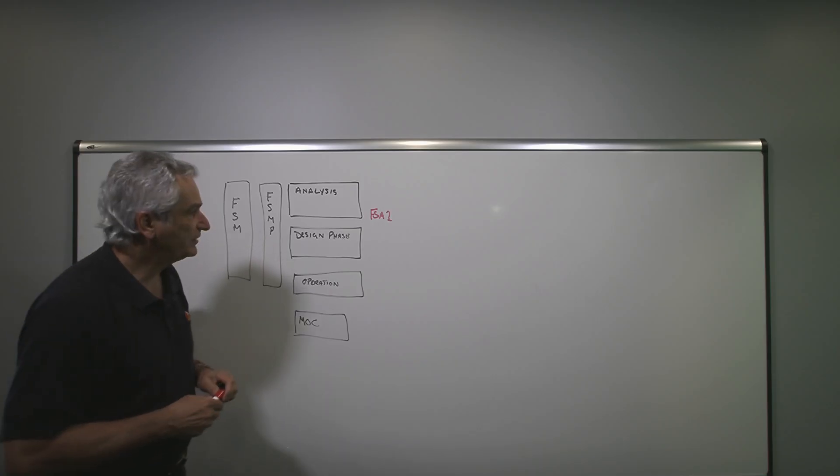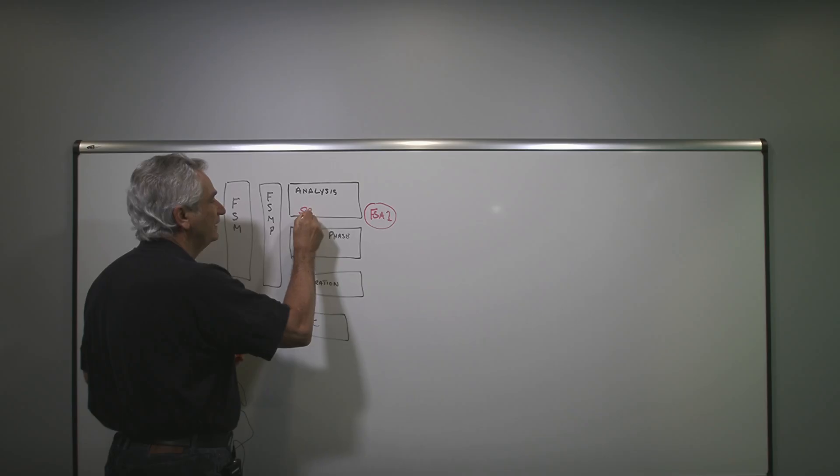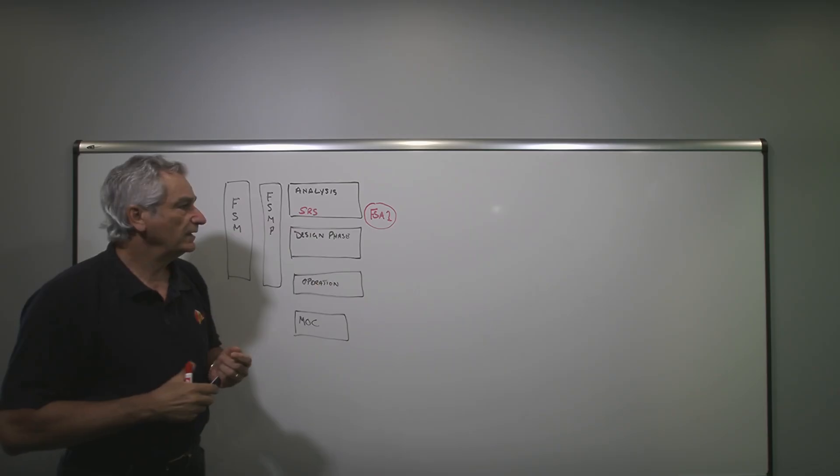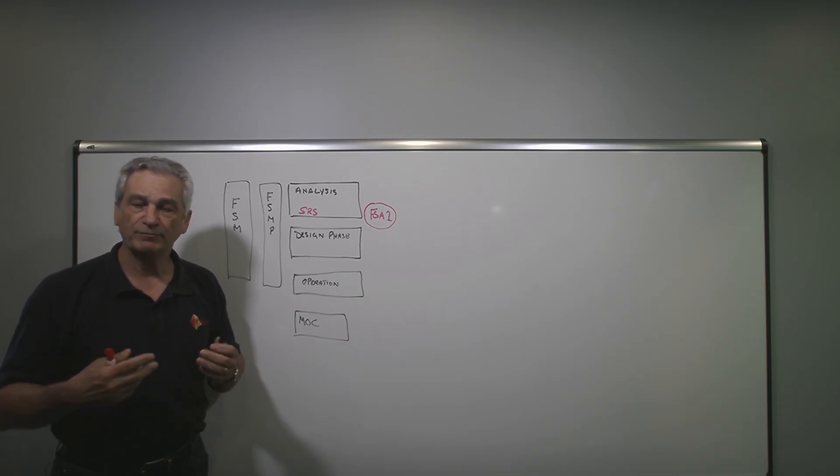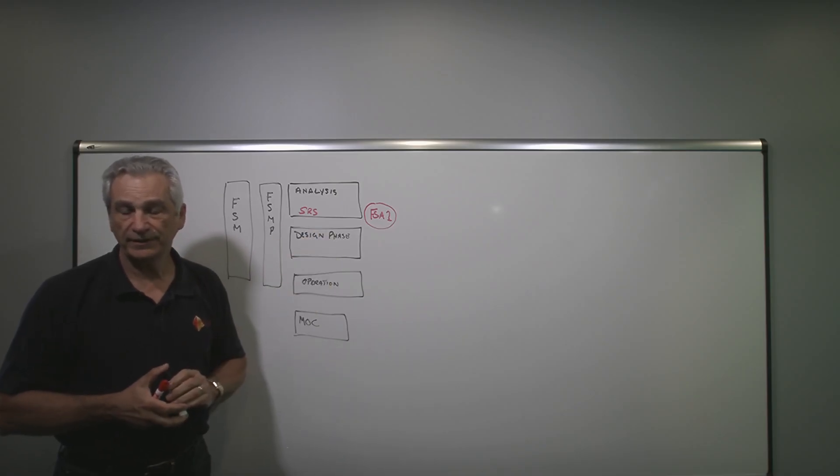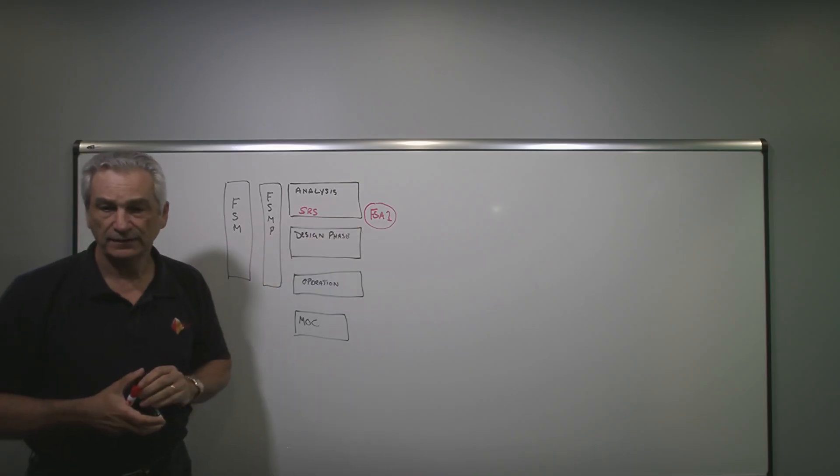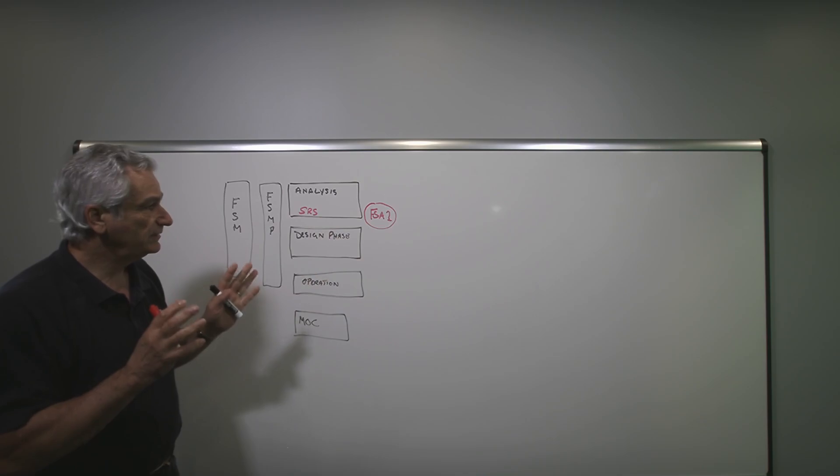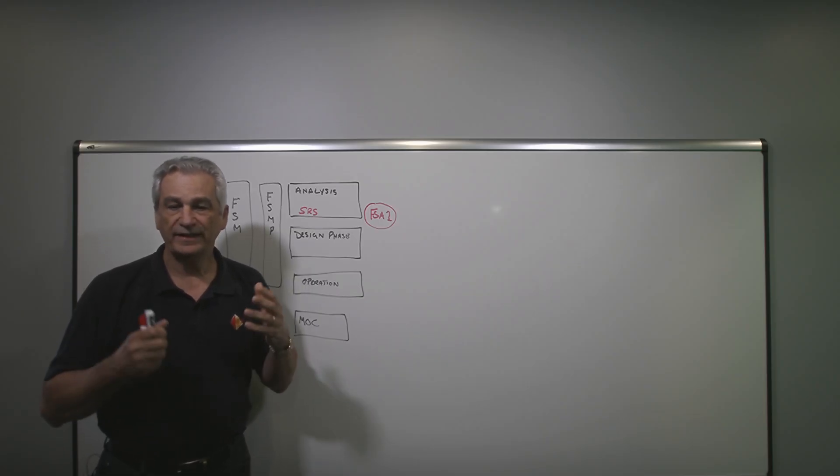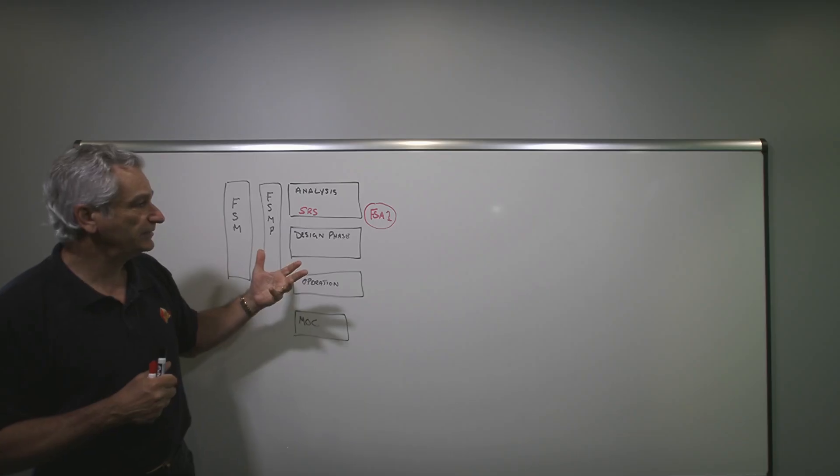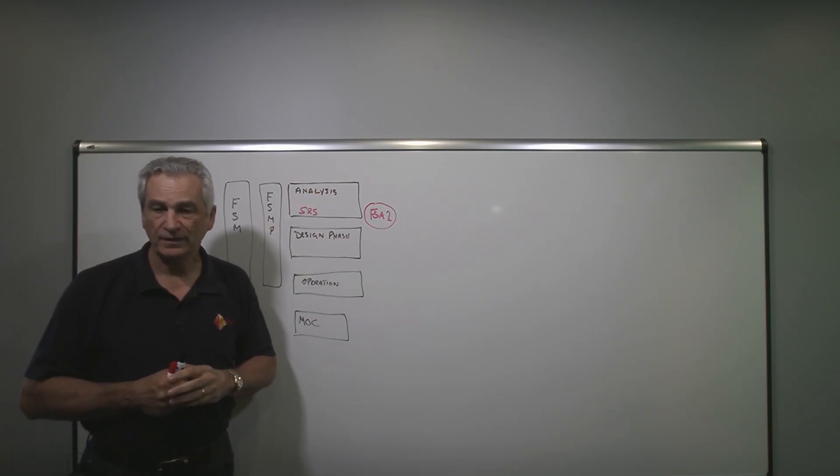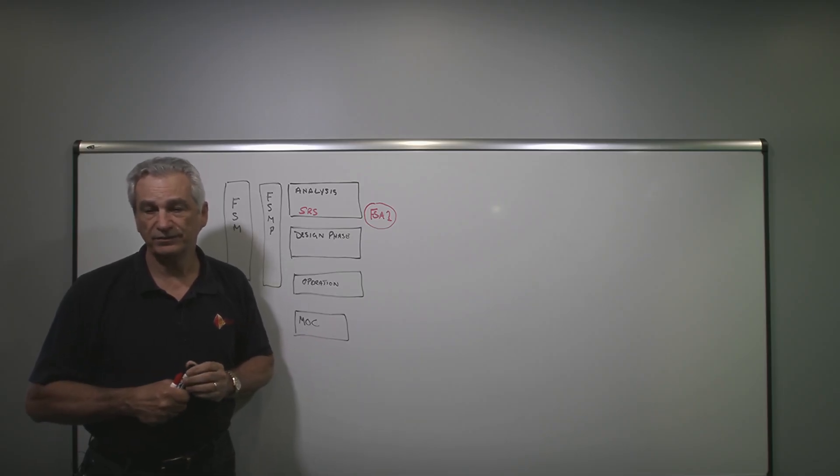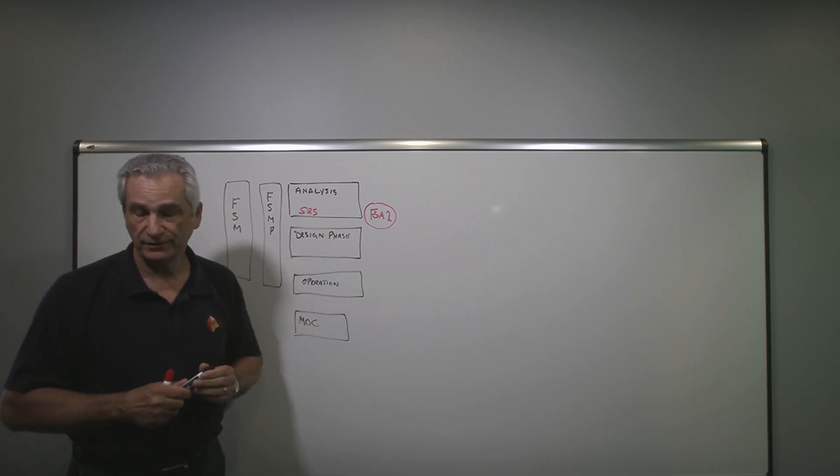The first FSA-1 is really to make sure have we captured everything properly in the SRS and do we achieve safety. If we've missed anything, if we've misinterpreted the requirements in terms of the risk reduction, if we haven't performed the SIL identification properly, if we've missed particular hazards and things like that, we should be able to pick that up at this point here before we go any further. Because as I said, the two things a functional safety assessment provides us with: number one, that independent cross-check. So it should be somebody or an organization that's qualified, competent to do the work, and is not involved in this stage. Typically, end users will turn to third parties like us to help with that, but they can do it internally themselves if they have sufficient independence.